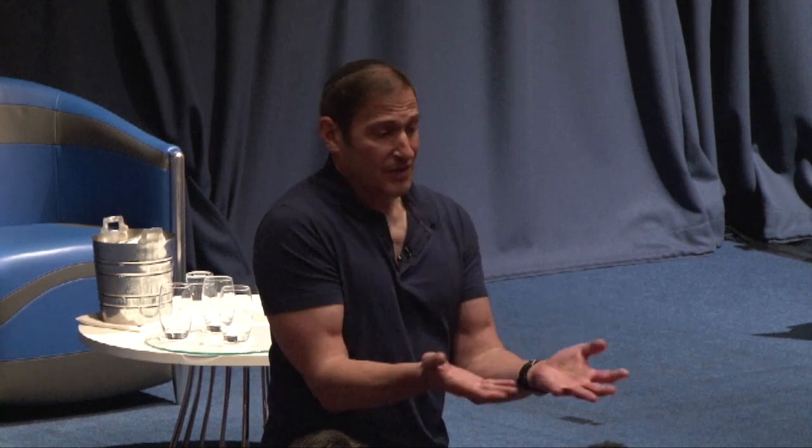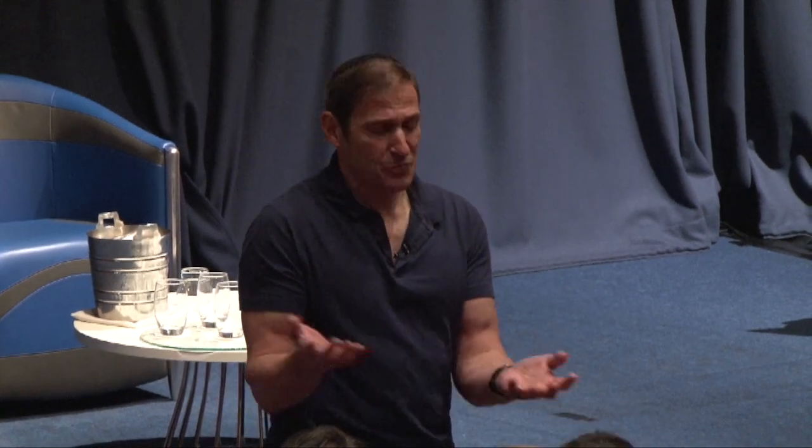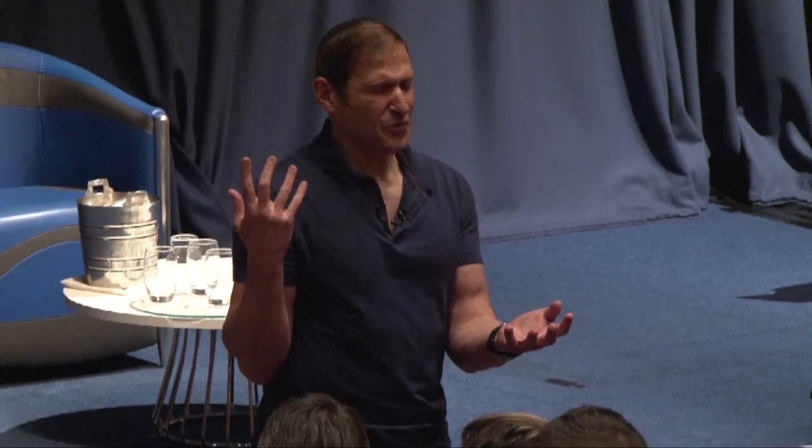I've made two apps. The first one I call a checklist. I'm not even going over that with this group. We don't have time. But the checklist is really there for an MRMD, an MRSO, and even an MRSE. The checklist will ask you questions like, will the device or implant or foreign body be exposed to significant gradient dBdx, dBdt? And an average person who's never been exposed to this will look at that and say, what? It's meant for somebody with domain expertise. It's meant for people that have an understanding of MR safety.